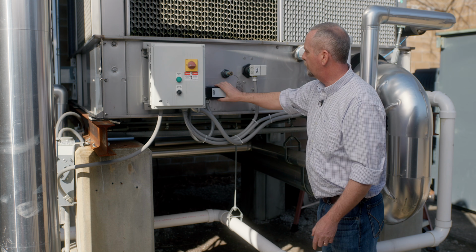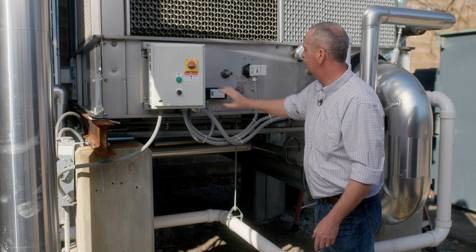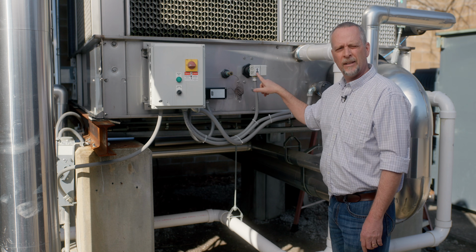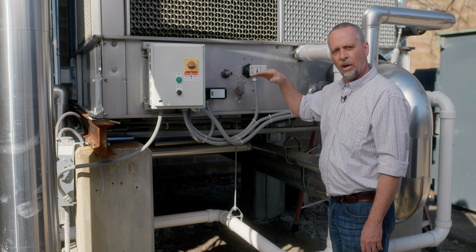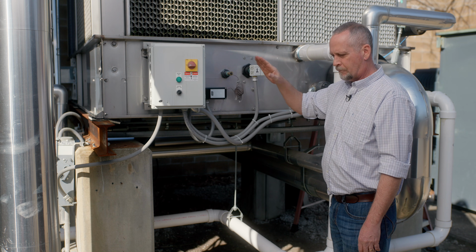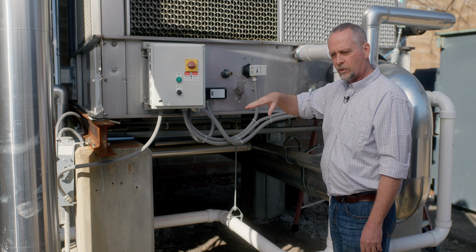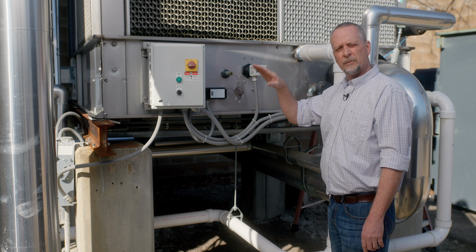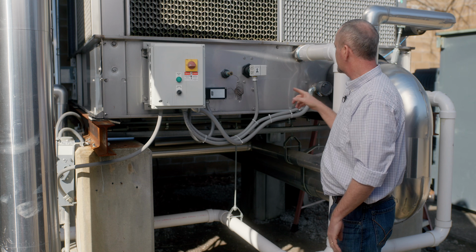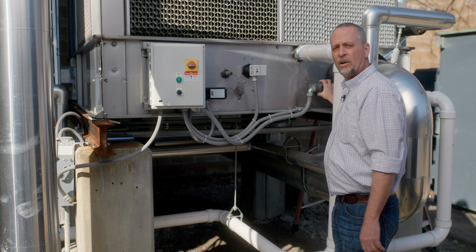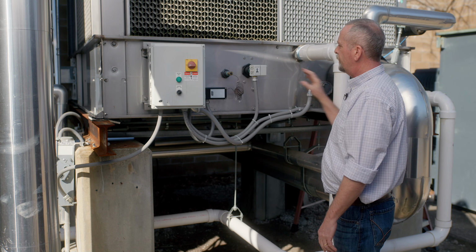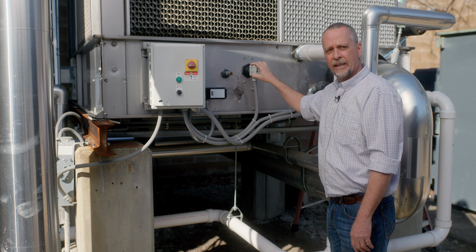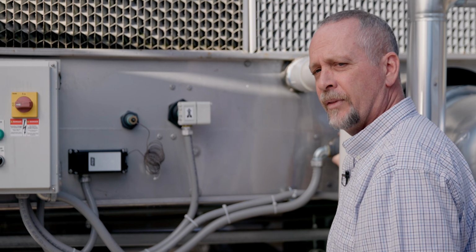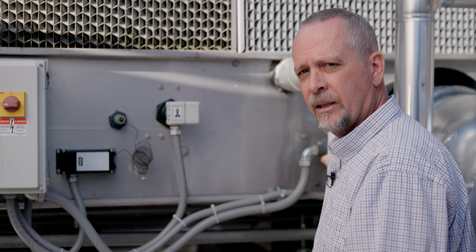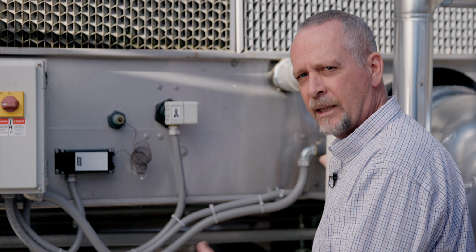Now there's another component that's critical to that basin heater operation, and it's this guy right here. That's a float switch. It's just an arm inside the tower that makes and breaks that way. So as the water level rises, the float switch comes up and makes a contact and says, I'm safe to start this heater. It's a very important part. The reason for that, you would never want to run this heater without water in the basin because the heater will burn up. It needs water to keep it cool.